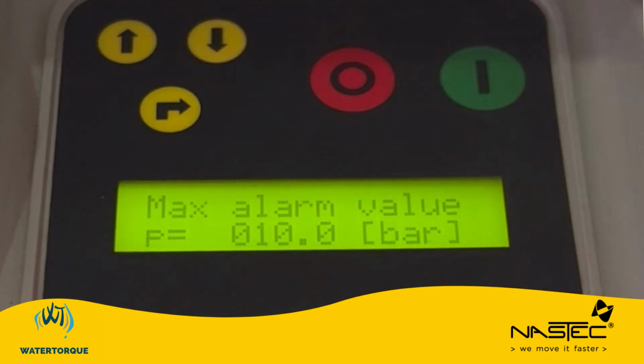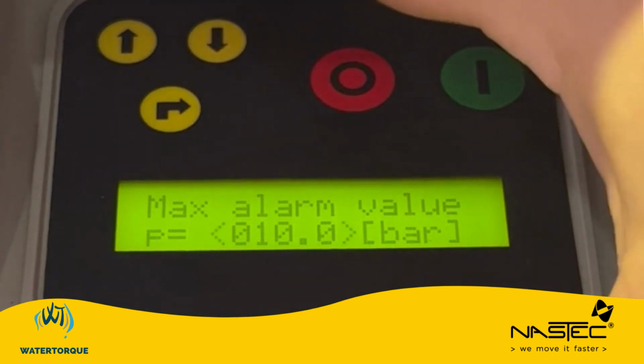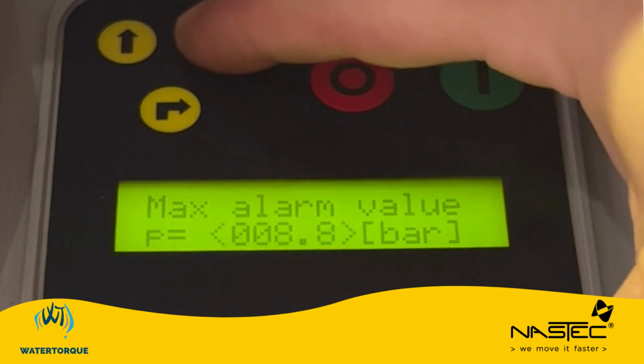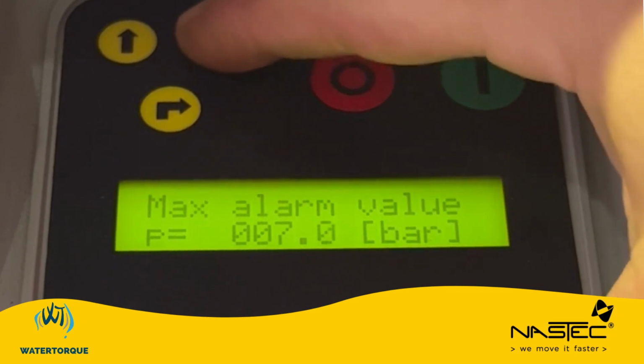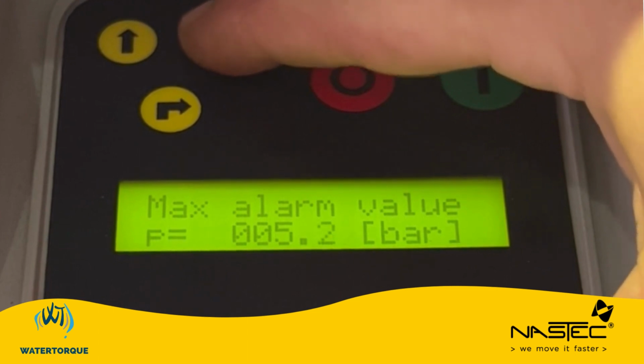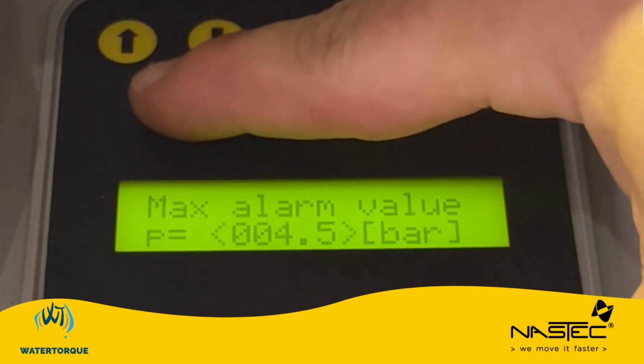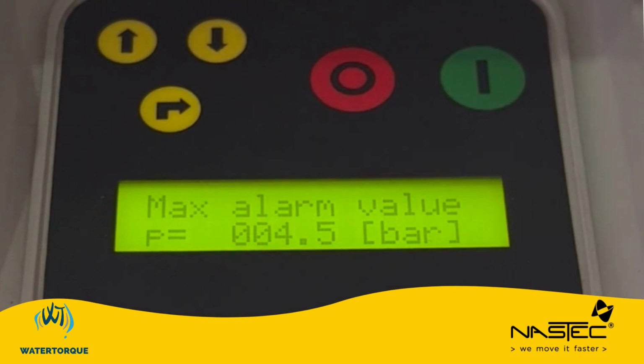Now if we move down to max alarm value, out of the box, the max alarm value is set at 10 bar. This particular pump has a maximum head of 5.5 bar. So for this instance, we're going to set our max alarm value at 4.5 bar. The way we do that is we hit the enter button and bring this down to 4.5 bar, and we hit enter. Max alarm value effectively is the pressure at which the pump will shut off when the system achieves that pressure, so the high pressure value.